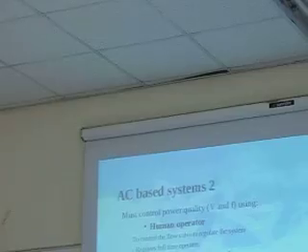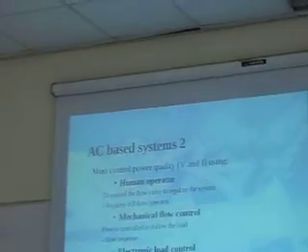So you could also have a mechanical flow control, so you could control the flow through the system to follow the load. Problems with this, generally why it's not done, it's relatively slow to respond. So if you turn on a 2 kilowatt heater, it might not work quick enough. Also it needs quite a lot of maintenance. You've got a flow control valve, which is quite a heavy bit of kit, especially if you've got 20 kilowatts of water pushing through it. You have to control that. It's just difficult to do.